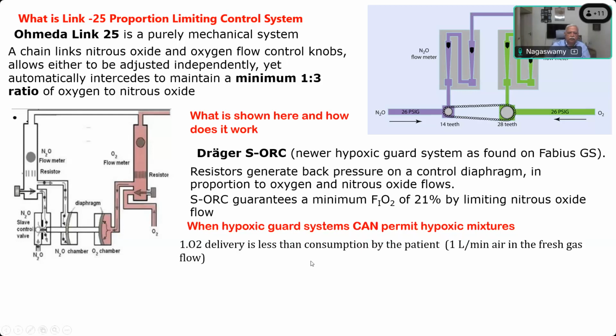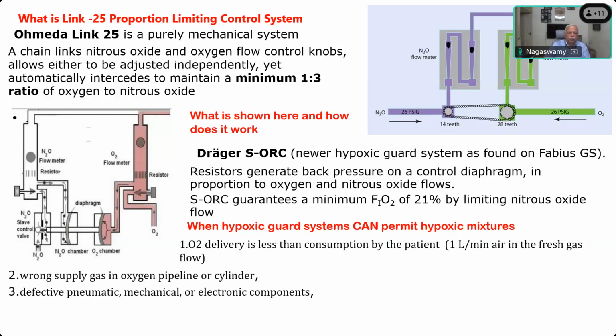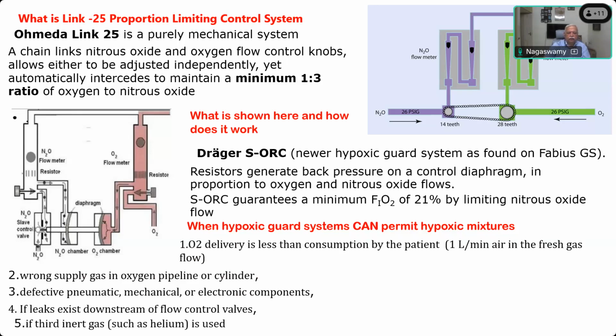The fresh gas flow, number one. Then wrong supply gas in the oxygen pipeline or cylinder. Defective pneumatic, mechanical or electronic components. If leaks exist downstream of the flow control valves. If a third inert gas like helium is used. So in all these conditions, despite having a hypoxic guard system, you can still deliver a hypoxic mixture.